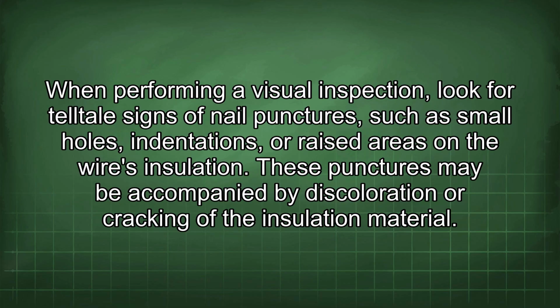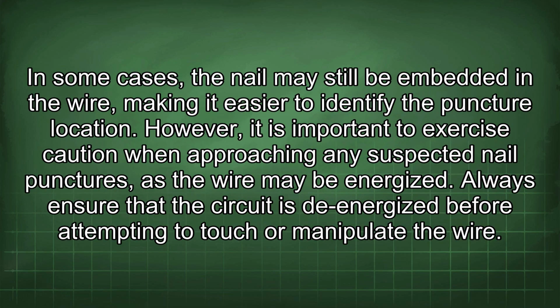When performing a visual inspection, look for telltale signs of nail punctures, such as small holes, indentations, or raised areas on the wire's insulation. These punctures may be accompanied by discoloration or cracking of the insulation material. In some cases, the nail may still be embedded in the wire, making it easier to identify the puncture location. However, it is important to exercise caution when approaching any suspected nail punctures, as the wire may be energized. Always ensure that the circuit is de-energized before attempting to touch or manipulate the wire.